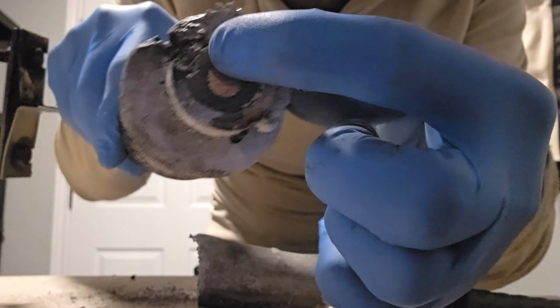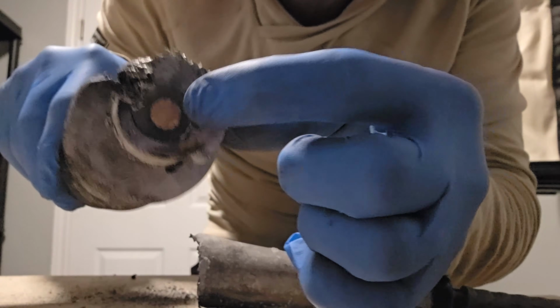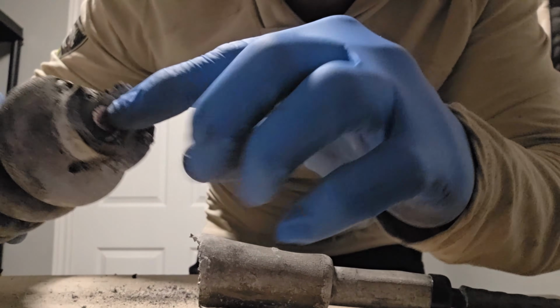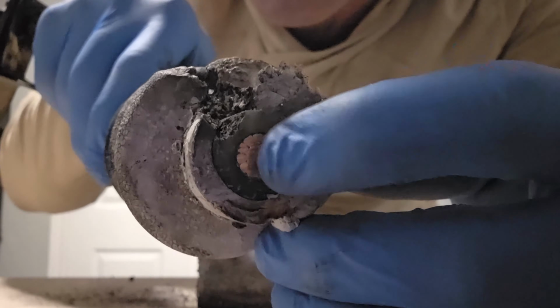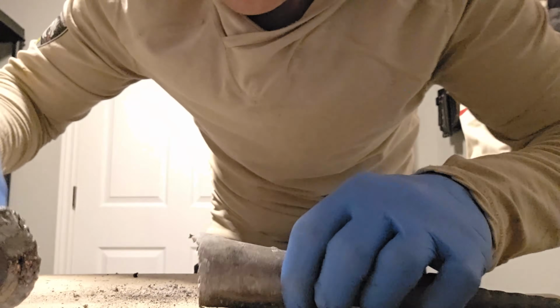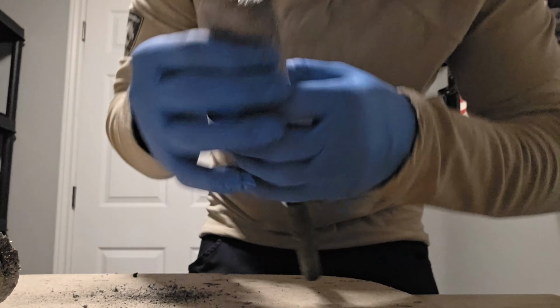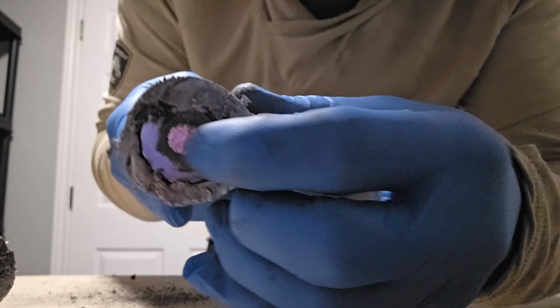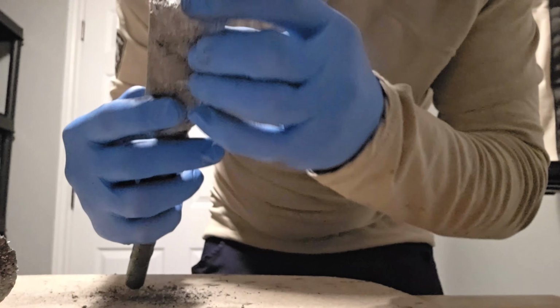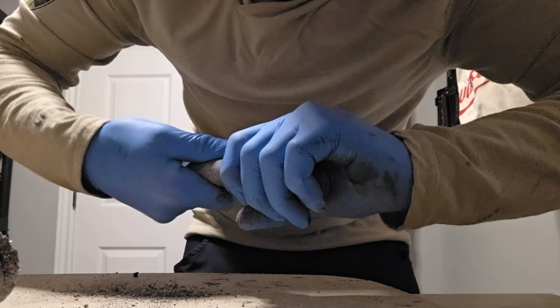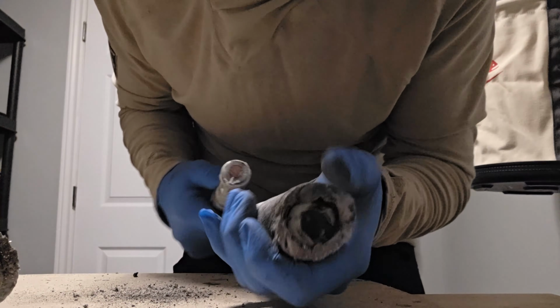Interesting. So you can see the insulation still fully intact around the copper right there. The arc was traveling on the outside, so the fault started a little bit higher up in the cable. Same with this guy here, it's still intact. I can see some damage on this top side, so let's see if that might pull right off. There we go.